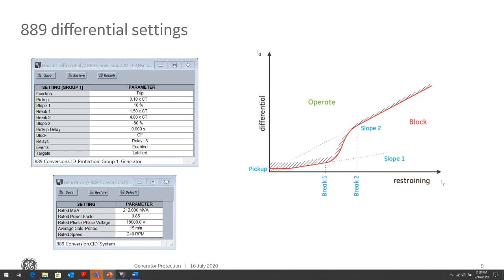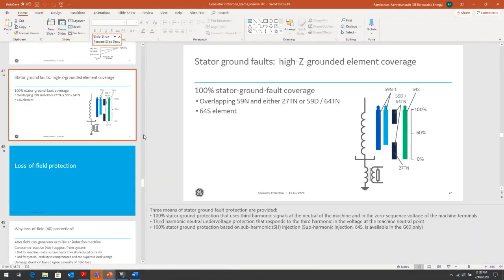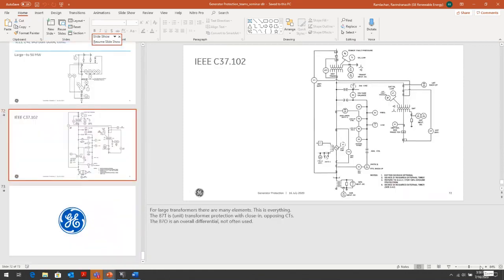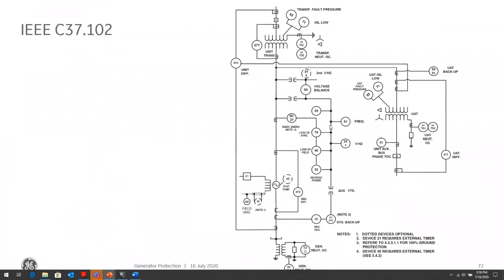So the way that you really need to do that sort of backup protection is with something that uses voltage as a restraining quantity. So you either use a voltage restrained 51 element or a phase distance element. Correct. And that's what we've seen in that slide on the C37.102. As Terry mentioned, we didn't talk much about the 51 or the 21 because it's mostly for backup protection. It's at the bottom here, 21. So it's a substitute. Either one will work.